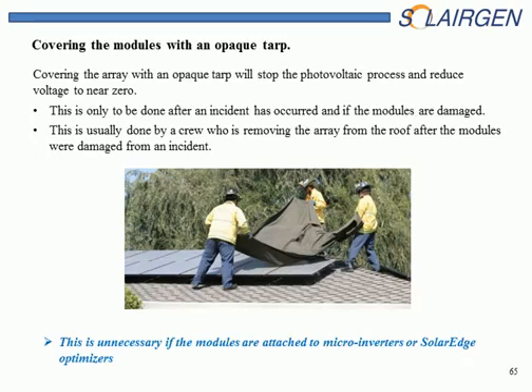Covering the modules with an opaque tarp will reduce the voltage to zero, so it makes it safe on the DC side. I wouldn't do this until after the incident had occurred. The tarp could be a hazard itself. So this is usually done by a crew that's removing the PV array after something has happened and they're having to work on it. So this is a good maintenance procedure, but not an emergency procedure. Of course, it's unnecessary if you're using microinverters or SolarEdge optimizers.